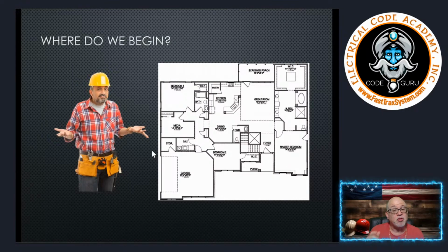Right? Now, in the 2023, guess what? Even your garage square footage has to be taken into consideration. Okay? There are a lot of people that are adapting their garage as a habitable space or for future use that is not just a garage. So that was a change in the 2023 to remove garage from the list of things which you exclude from your square footage, right? So that means it's got to be included in my calculation.